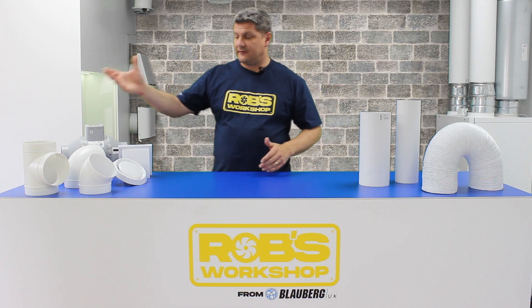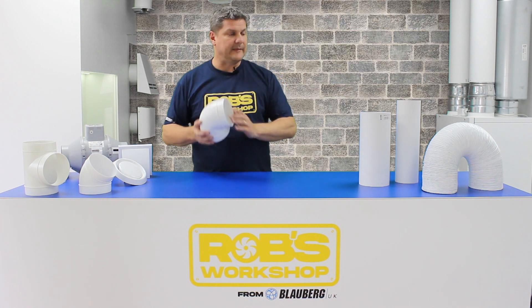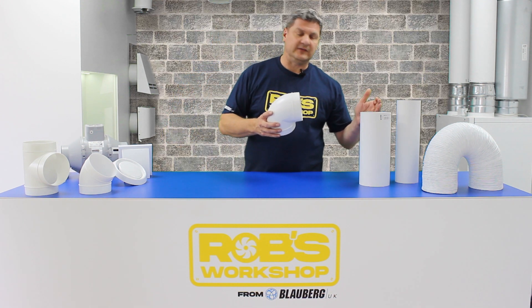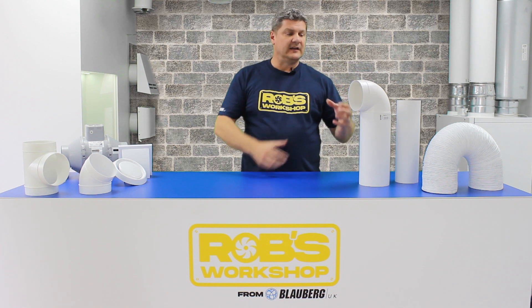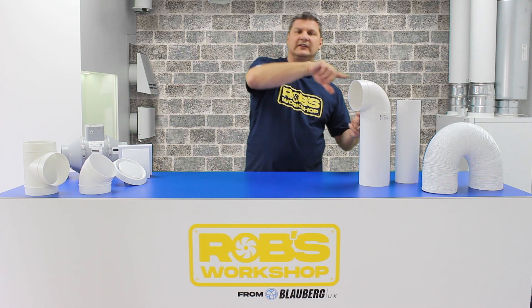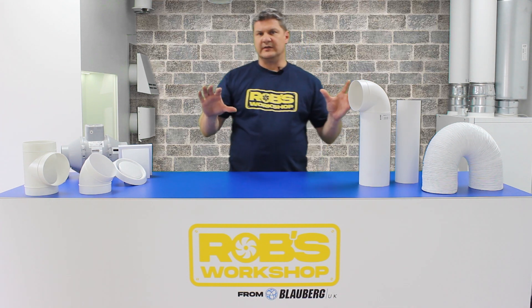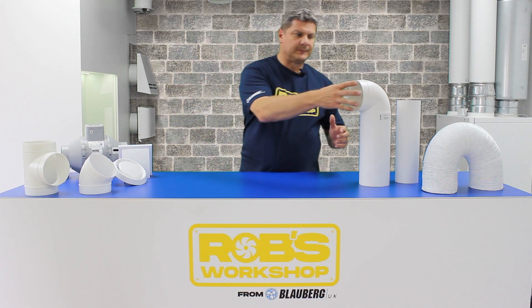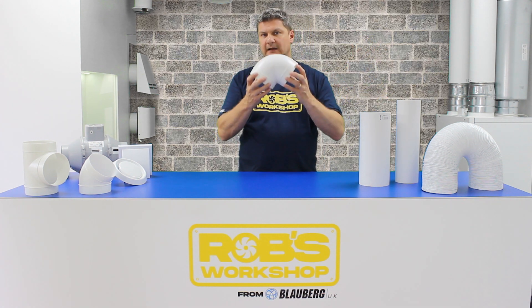Because of that, if we take for example a 90-degree bend — this is a 125mm 90-degree bend — and take 125mm rigid PVC pipe and put that inside, it will fit inside to make a seal. You can then use a mastic seal to seal that up, tape it up, and you're ready to continue with your duct run. So the ductwork is male, and the fittings are female.